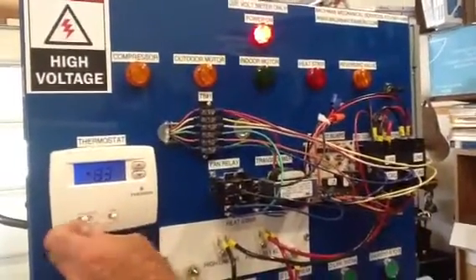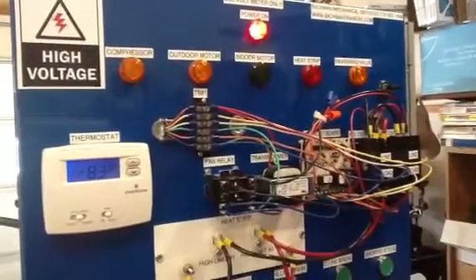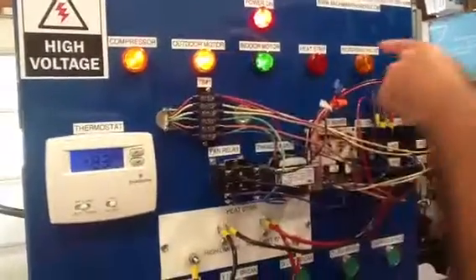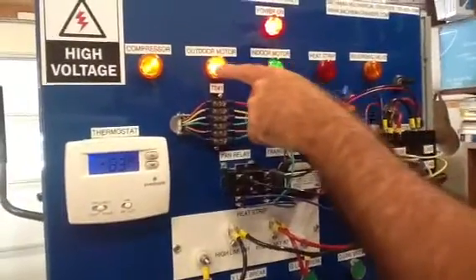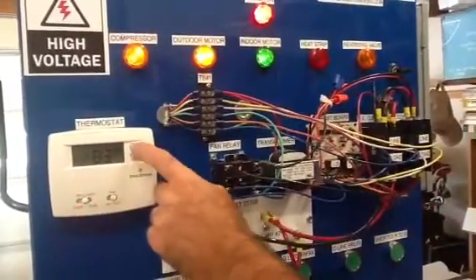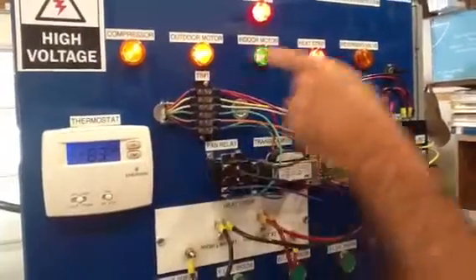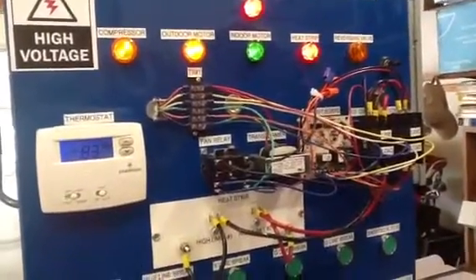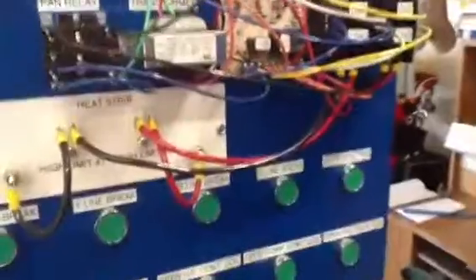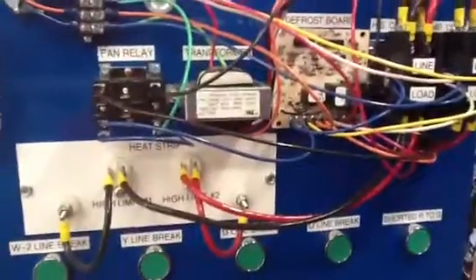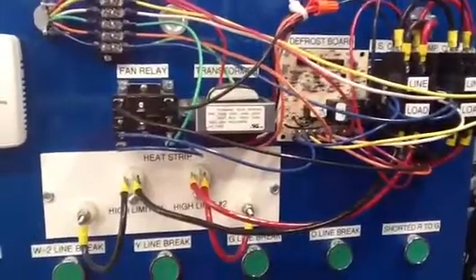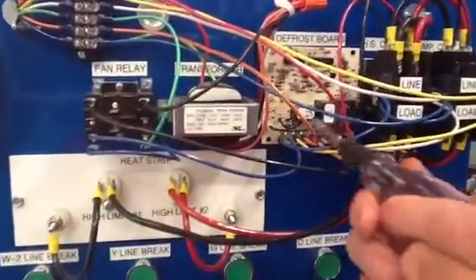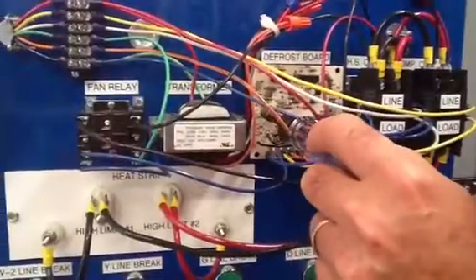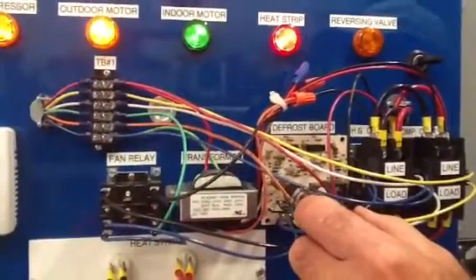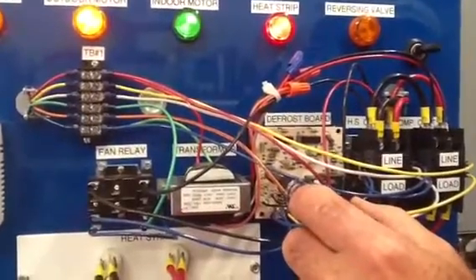Fan manipulates correctly. We are in a first stage heat call. There's first stage. Reversing valve is off. Indoor motor is running. Outdoor motor is running. Compressor is running. And now we are going to call for second stage heat. Second stage heat is energized. Now, last but not least, on my trainers, you must initiate and terminate defrost. Basically, you have to check defrost to make sure that everything is working correctly. And the way you do that is you short across the two test terminals. Use a 5/16 nut driver or a 1/4 inch nut driver without putting any pressure on the terminals.